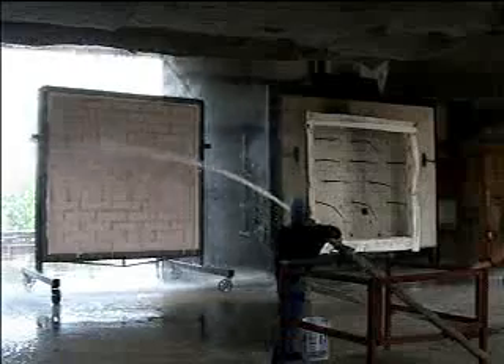As you can see in the comparison between the gypsum wall assembly and a masonry wall assembly such as this, the performance is dramatic. This wall was able to withstand the fire exposure for two hours and then immediately face that water impact — and when we did that, this wall held up.